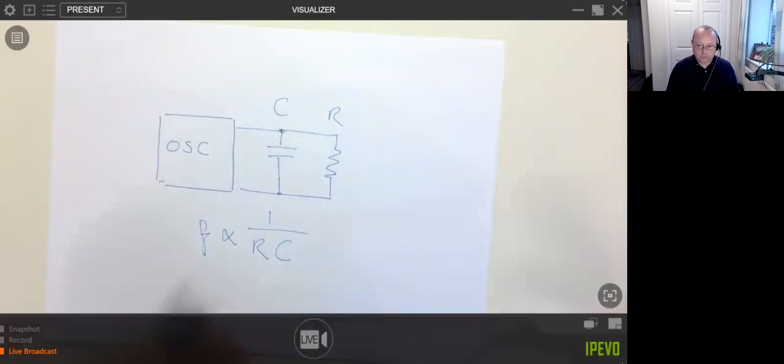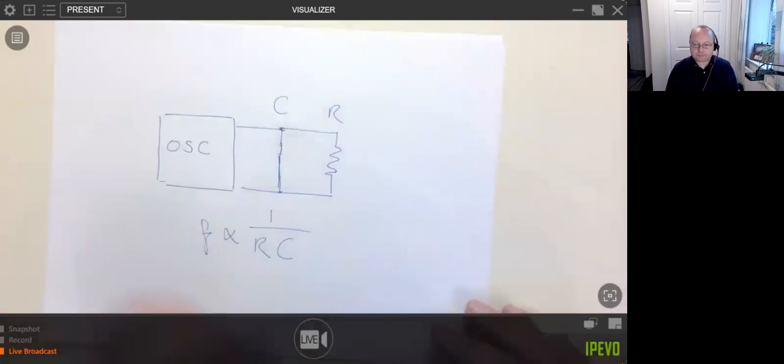If I had a short circuit, I've then pretty much got a wire. Is that then going to cause me a problem with my medical device? That's the question. The product I was working on was a low power diathermy for taking out thread veins. It was cosmetic surgery.